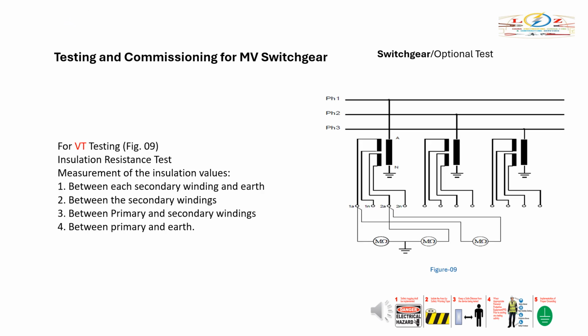For VT testing, insulation resistance test as shown in the arrangement drawing. Measurement of the insulation values: 1. Between each secondary winding and earth. 2. Between the secondary windings. 3. Between primary and secondary windings. 4. Between primary and earth.